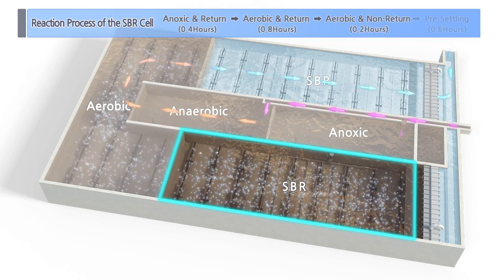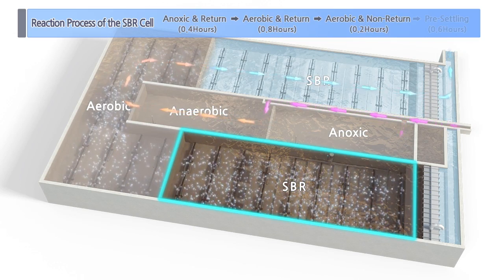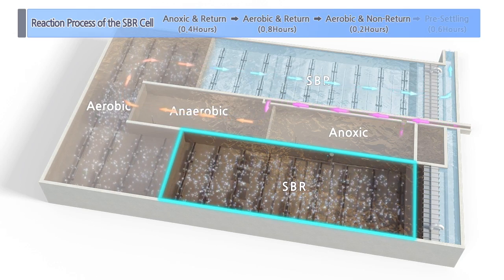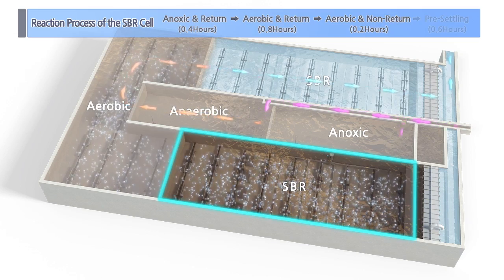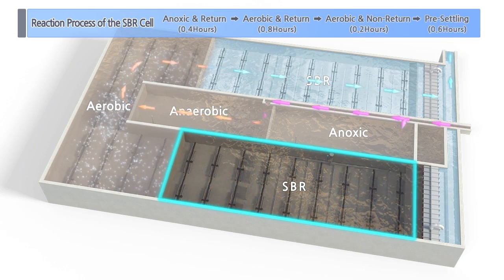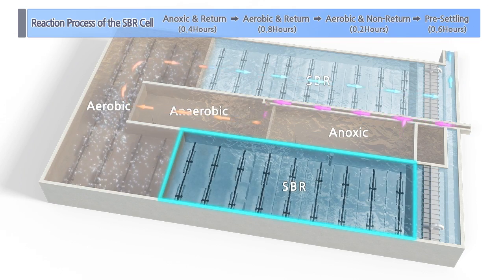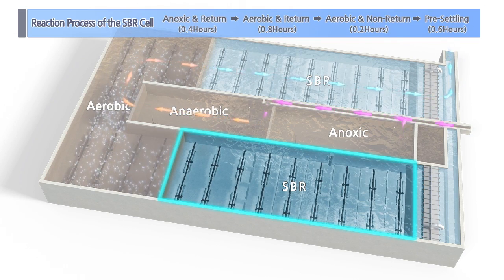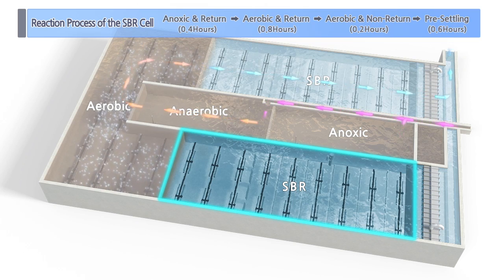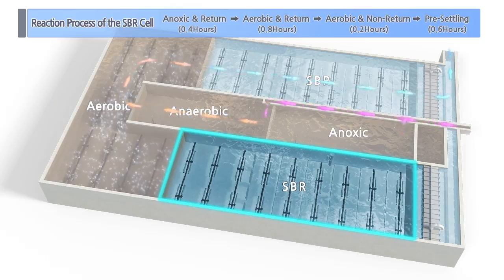Next, at the aerobic and non-return stage, the return process is stopped by closing the return valve and stopping the pump, while the aeration condition continues by supplying air continuously. After the aerobic and non-return stage, the next step is pre-settling, in which the solid-liquid separation occurs within a short period of time in a static settling state, where the SBR cell is in off mode.